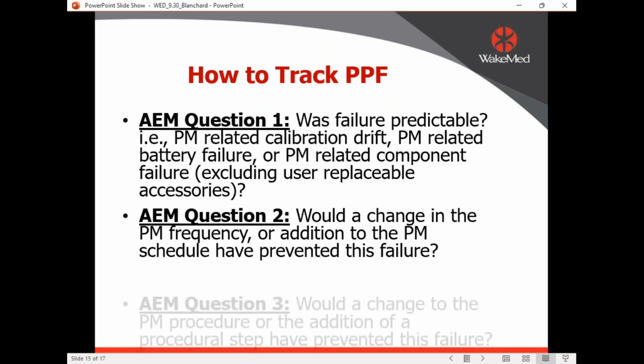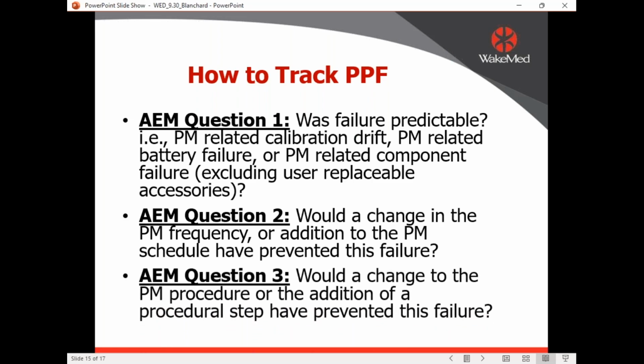And then the last question, would a change to the PM procedure or the addition of a procedural step have prevented this failure? So should we add another step? Should we take away a step? Any questions on that? See the value of doing something like that? What that does is it kicks out a report immediately. I'll immediately get notified by an email pop-up saying somebody answered yes to this, and I'll look it up, see what the model was, and start seeing whether we have other technicians saying the same thing. I've caught a lot of devices and made a lot of changes, and it's constant.